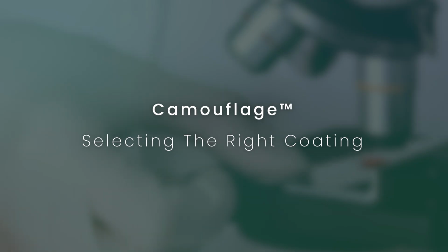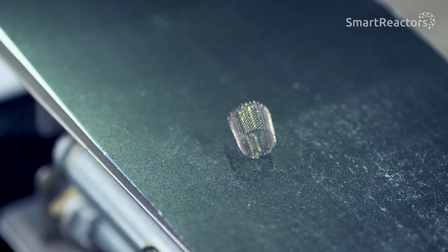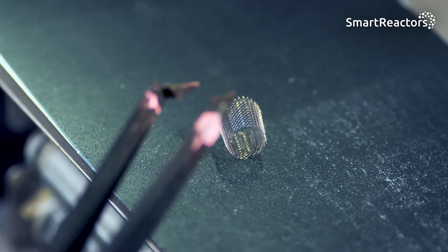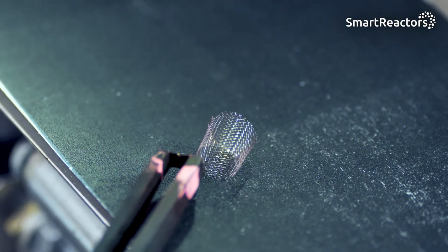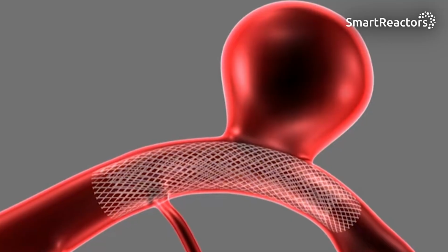When it comes to selecting coating, it all starts with understanding your application. What interactions will your device have with the body? What will it come into contact with? How long will it be used? What are the risks with an adverse reaction to the device and to the device surface? What are the expected off-label uses or indications you need to be concerned with? What are your materials and substrates?